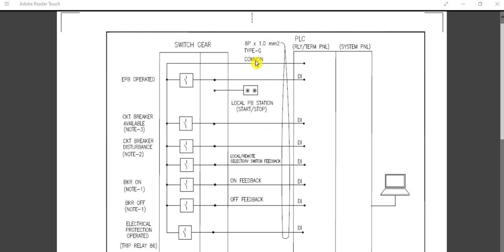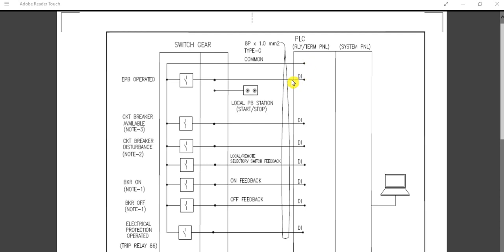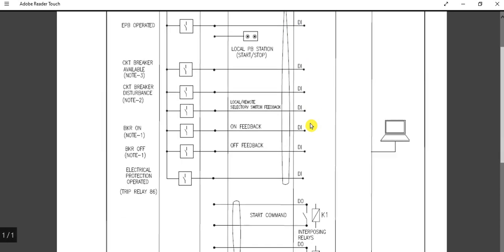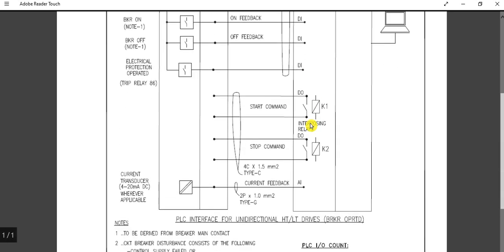For this purpose, we have considered an 8-pair, 1 square mm cable. The total number of DI signals is seven individual signals plus one common, giving eight pairs total. So an 8-pair, 1 square mm cable connection is used to convey all DI signals to the DCS or PLC cabinet.